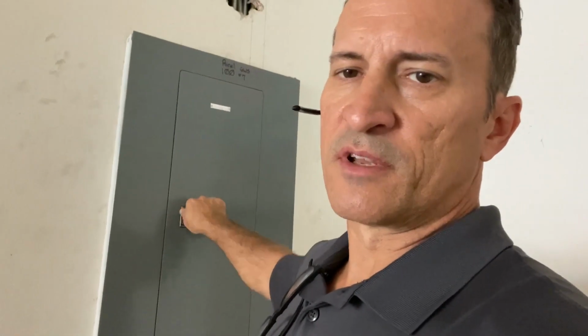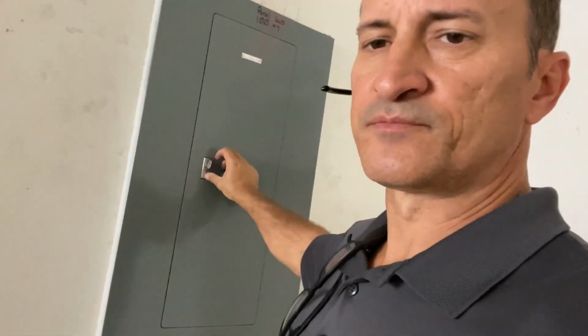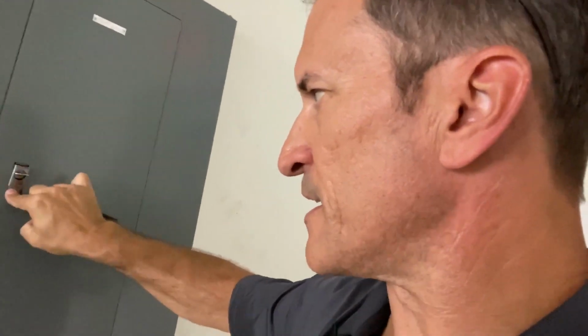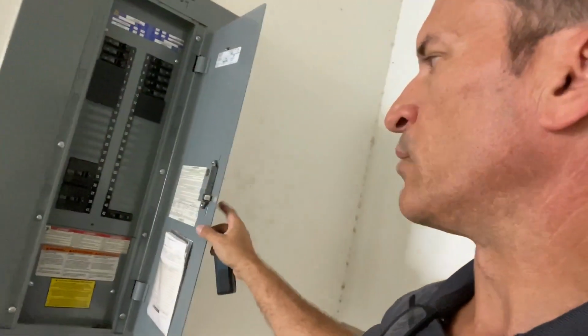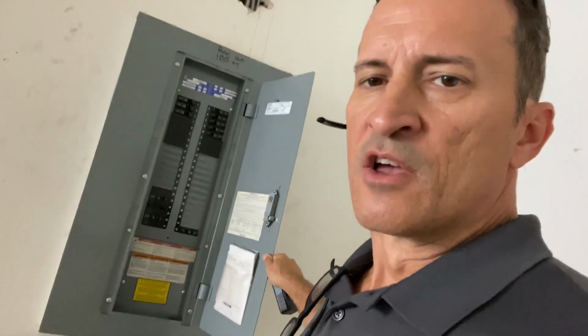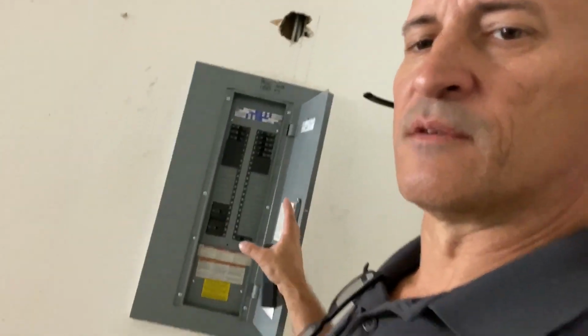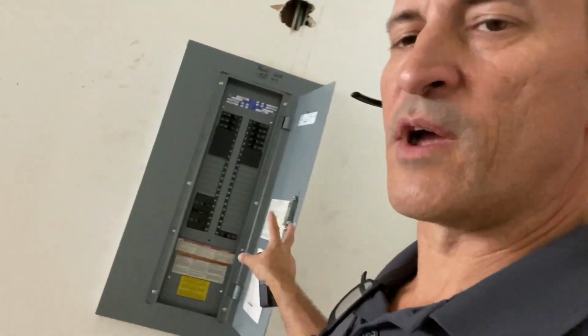Next, let's look at the electrical panel. In a tenant improvement, the code requires that, just unlock it and push this handy dandy button here. The code requires that we have a panel inside the suite. So if you find a suite that they've demised illegally, and they've put these demising walls in, and there's no electrical panel, then it's not done legally. There needs to be a way for the suite to turn off their panels. Unless you're in some kind of an office building where all the electrical panels are in one room, that is an exception, but if it's a standalone suite in a shopping center, you need that panel.